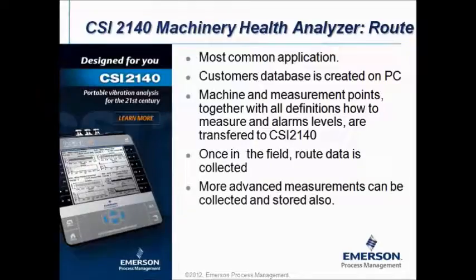The second application is called route, and without any doubt this is the most common application of the analyzer. So what is route mode? The customer will create a database on a PC. In the database you configure your areas, your machines, your measurement points, the way you want to collect the data, your alarms, and all this information is transferred into the CSI2140 analyzer.